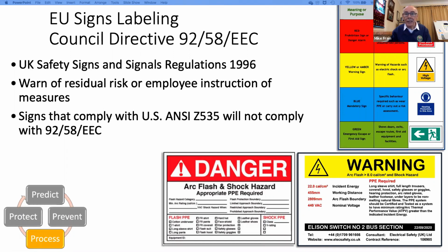But arc flash labelling is not a mandatory requirement, unlike some of the consensus standards, particularly US NFPA 70E, where it's mandatory to field mark equipment. The European approach is less prescriptive, let's put it that way. Provide safety signs, yes, but only where there's a residual risk, where we've not been able to remove the risk by other means. So there's got to be a significant risk to health and safety of workers and others.